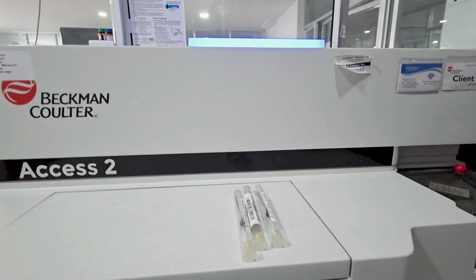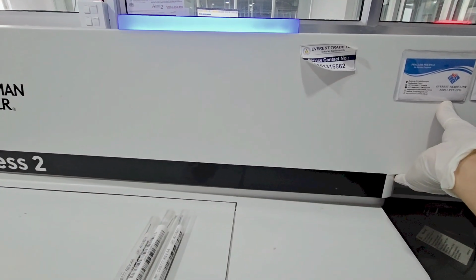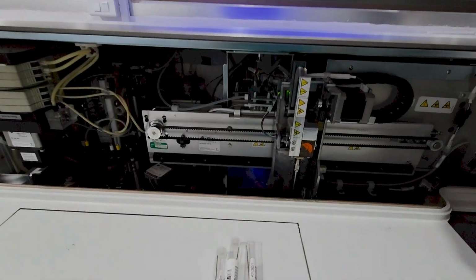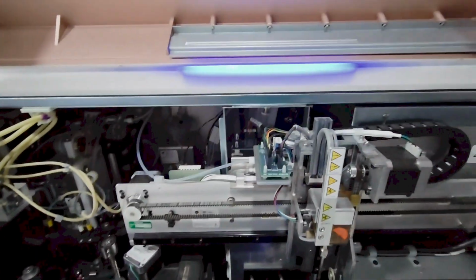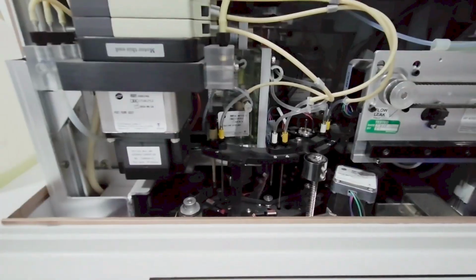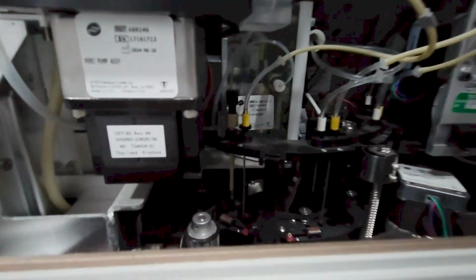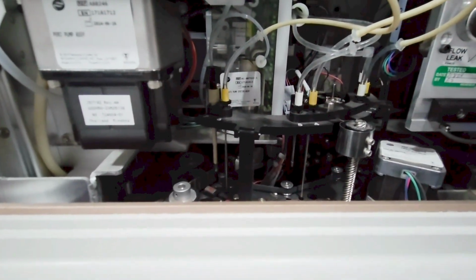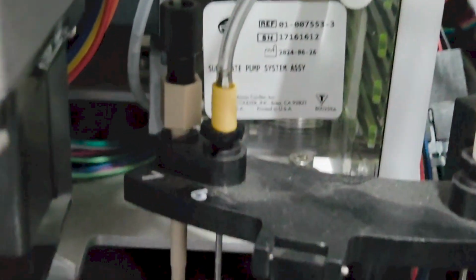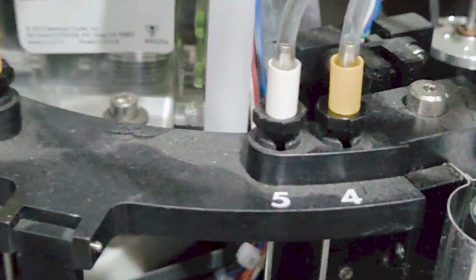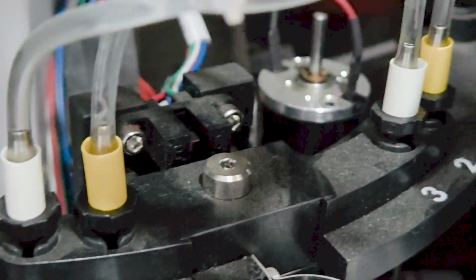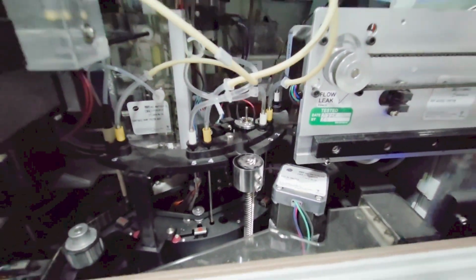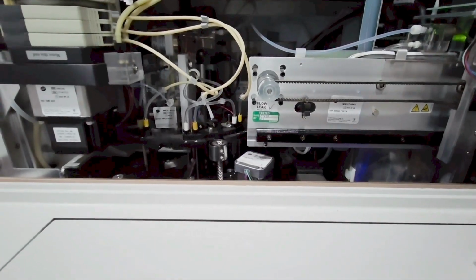We start the process by carefully opening the top cover of the Beckman Access 2 Analyzer. Once the cover is lifted, you can observe the internal structure of the instrument. Upon closer inspection, you'll notice several probes identified by their numbers. Here you can see specifically probe number 6, probe number 4, and probe number 2, each marked with yellow caps. These 3 are the aspiration probes that need to be replaced during weekly maintenance.